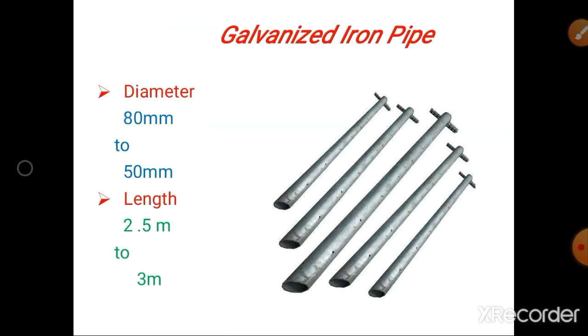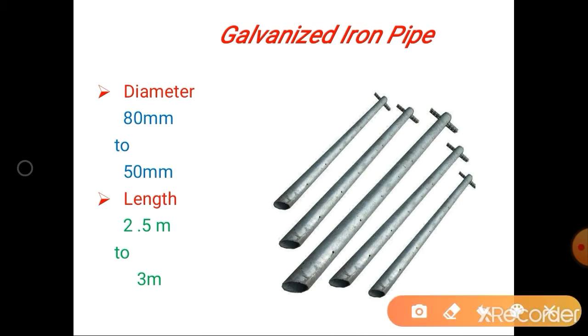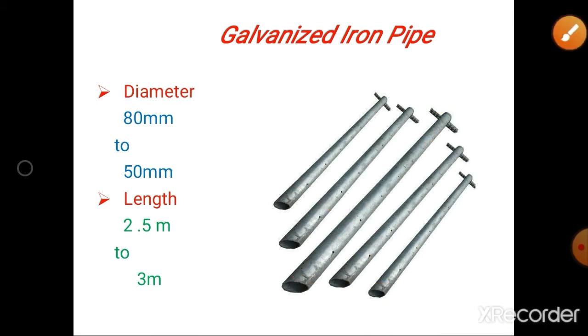This is the galvanized iron pipe used for pipe earthing. This pipe should have a diameter of 80 mm to 50 mm, and its length should be 2.5 meters to 3 meters. It has holes, the bottom end is narrow, and at the top we have the clamps where we connect the earth wire, the earth conductor.